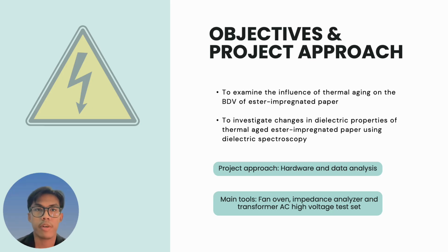The main objective of this project is to study how thermal aging affects the insulation performance of ester-based paper compared to the traditional mineral oil through some tests, which includes dielectric spectroscopy and breakdown voltage, or we call it a BDV test. So this project involves hardware experimentation and data analysis using key tools such as fan oven, impedance analyzer, and AC high voltage test set.